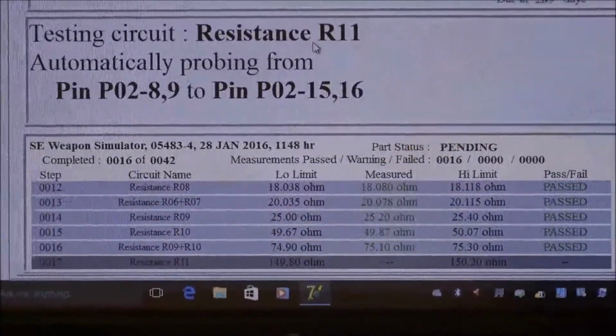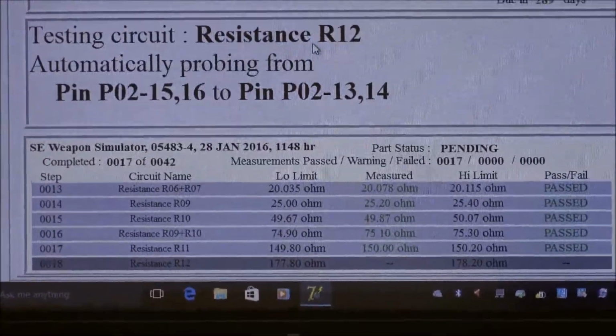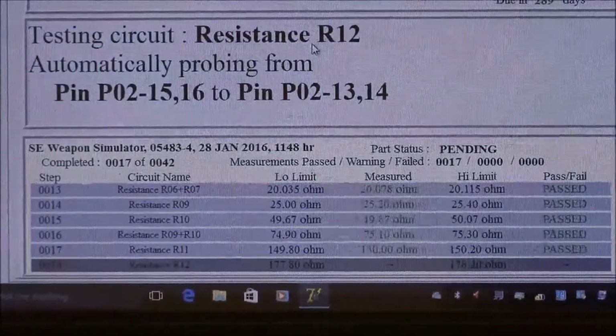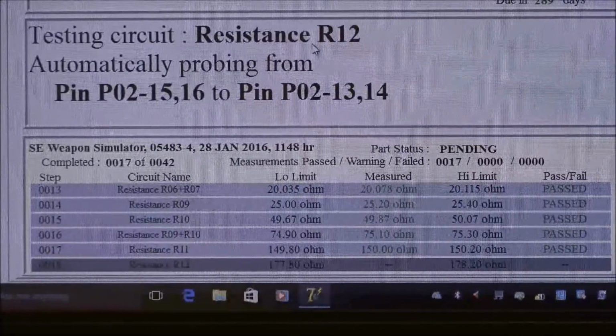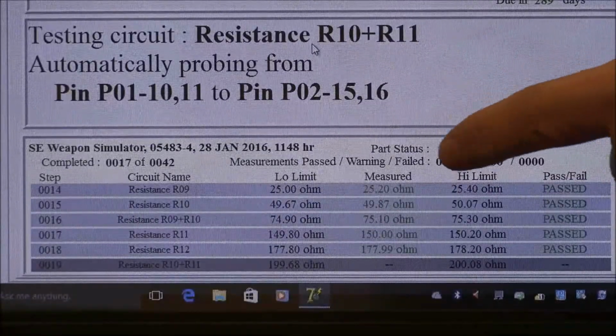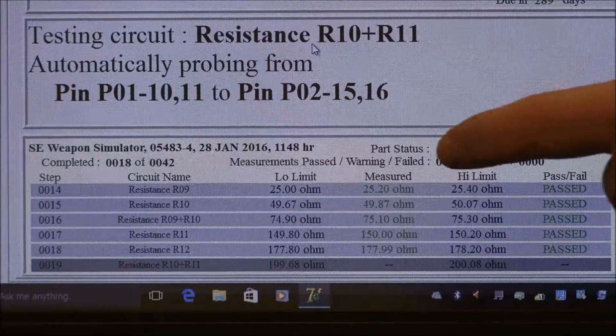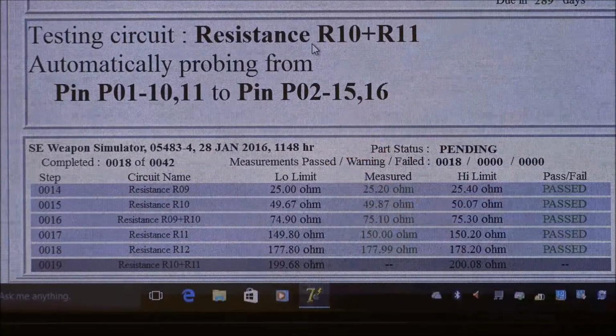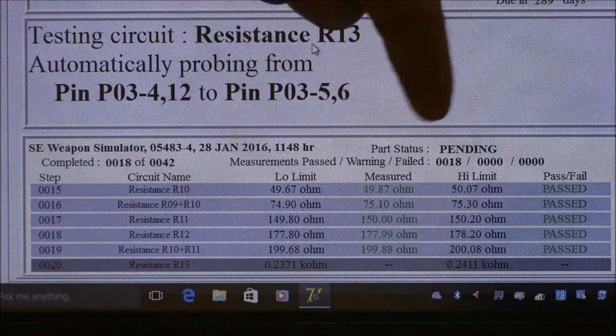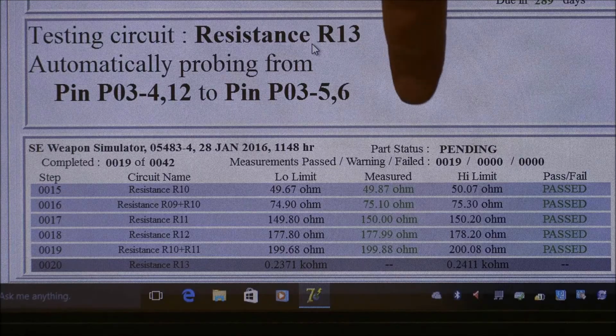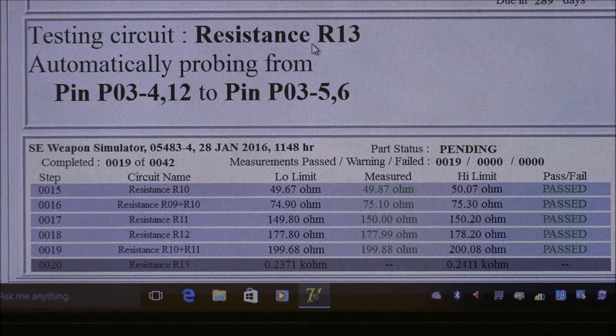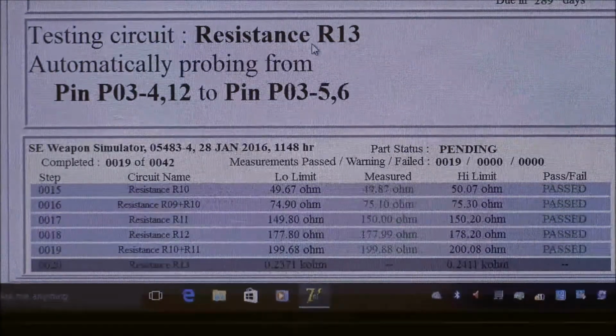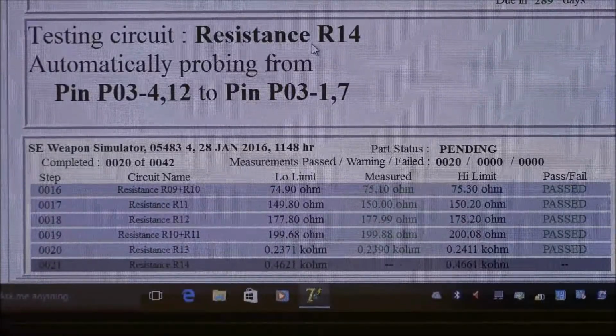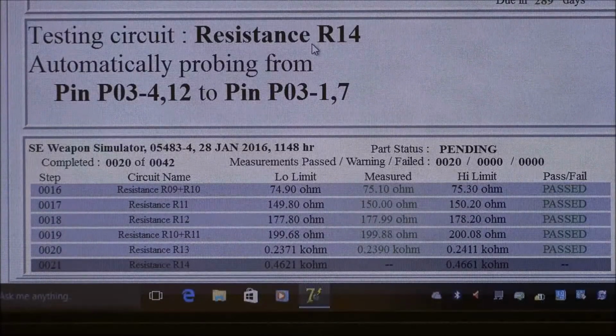Just above that, you see that the status of the part is pending. Hasn't finished all the tests, so I can't tell you if it's a pass or a fail part. Also, it tells you how many tests have been run, whether they've been passed, warning, or failed tests, and the counts associated with each one. Passing test is anything that was a test that was checked for verification or just measured. It says it passed.